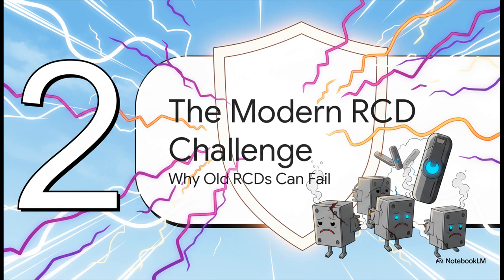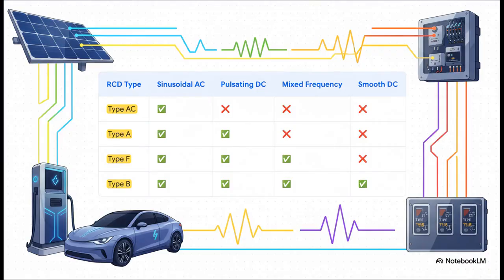But here's the thing. The electrical world has changed. The kind of devices we use every day are creating new, hidden dangers, and frankly, the older RCDs just can't keep up. Okay, pay close attention, because this table is absolutely essential for any electrical designer today. A classic Type AC RCD was built for simple old-school loads, so it can only detect those clean sinusoidal AC fault currents. But our modern electronics, they've completely changed the game.